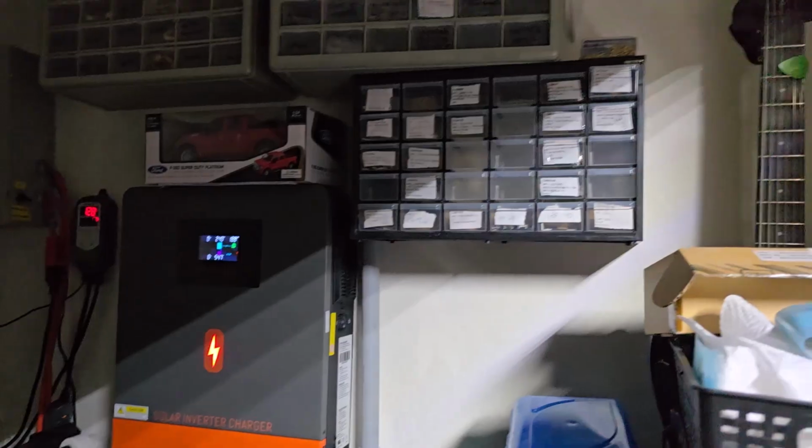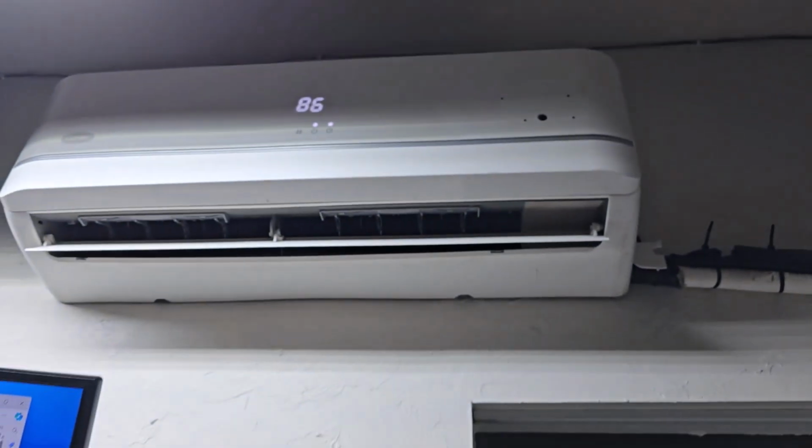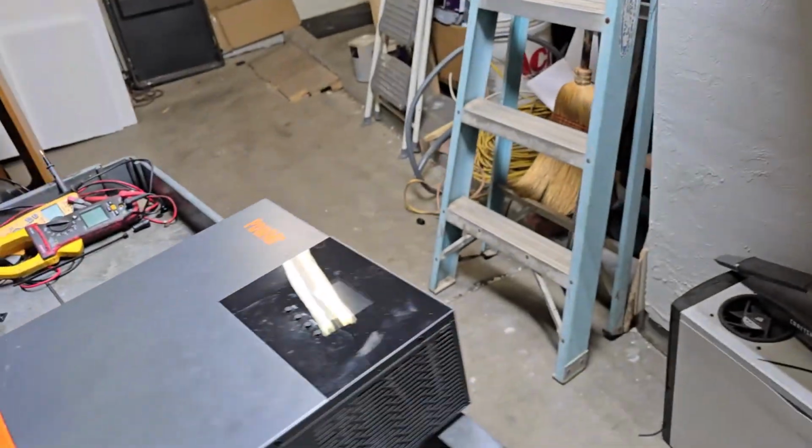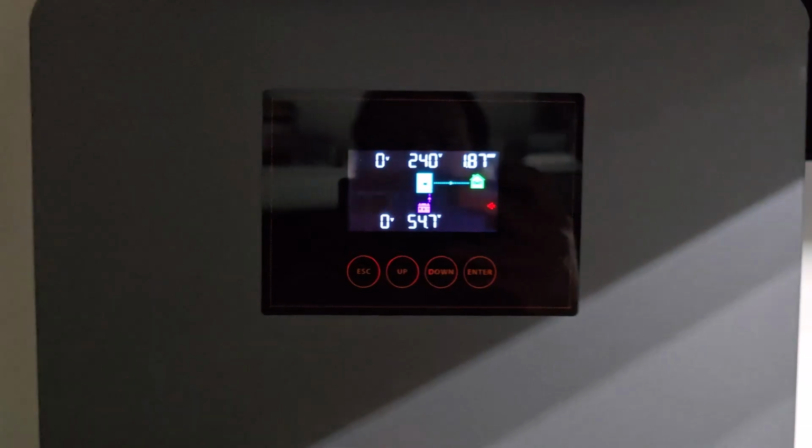So I got my ductless two heads. That one in the high wall running right now. And I realize if I set the temperature real high and get this return air temperature sensor where it gets a little influence, it'll actually cause it to ramp down a little bit earlier. So it's only 1.87 kilowatts.